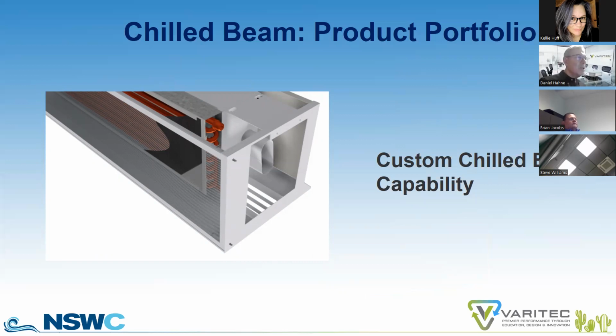One new technology that we have today, I don't have product literature on, but is very compelling, is a displacement ventilation active chill beam. I won't go into the details on that, but it really has attracted my attention as a very compelling idea and concept. And I just got off the phone the other day with our underfloor manufacturer.